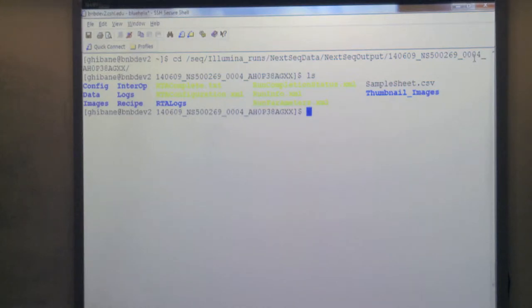The numbers like '14-06' are the run name format. When a run is done, the machine outputs the run name as: the date (year, month, day), then the name of the instrument - in this case NS500, but it can be a completely different name - then the experiment number (e.g., 0004 means the fourth run on that instrument), and then the flow cell name.